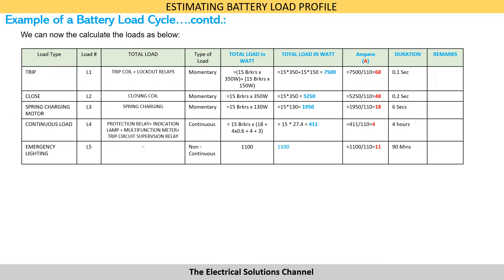The duration of the loads during tripping, closing, or spring charging operation shall be as given in the table, and this data can be obtained from the data sheet of the 11 kV switchboard. The continuous load on the battery bank is calculated by adding up all continuous loads — protection relay, indication lamps, multifunction meter, trip circuit supervision relay, etc. This works out to approximately 4 amps.